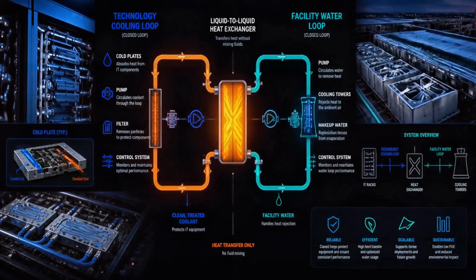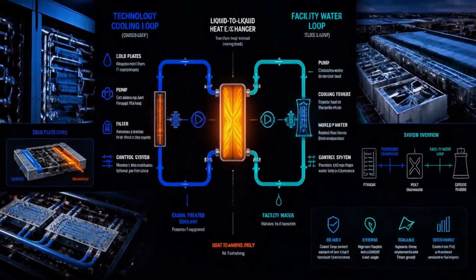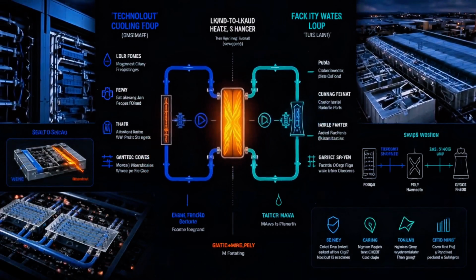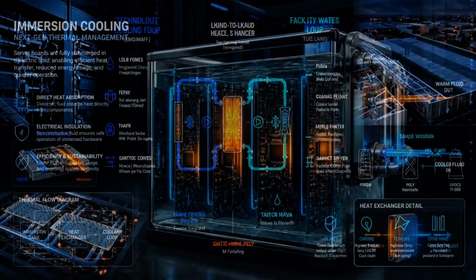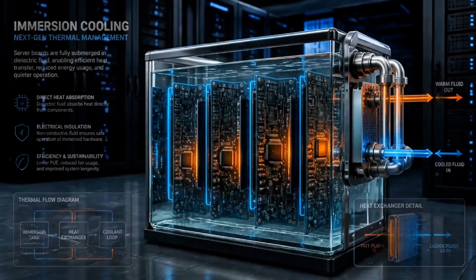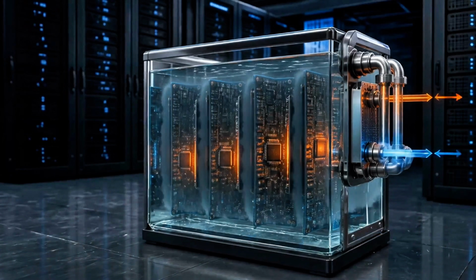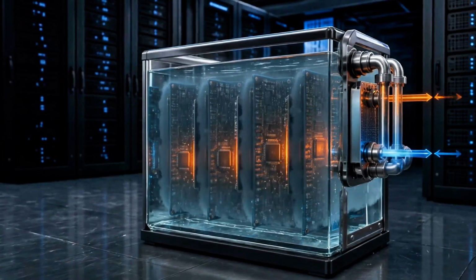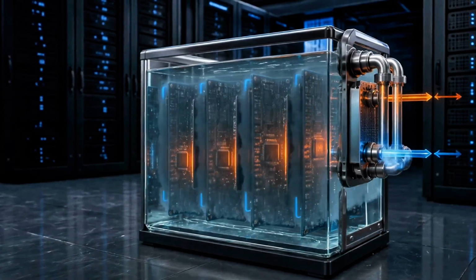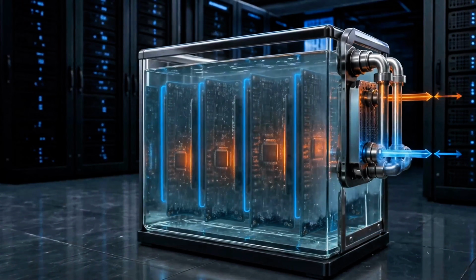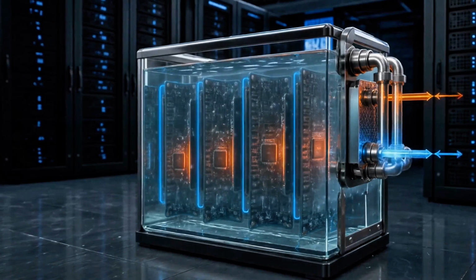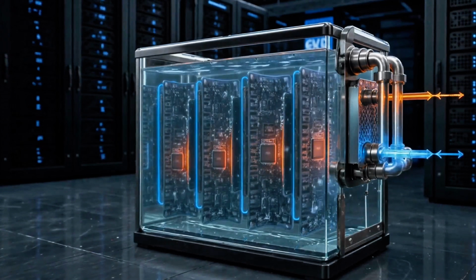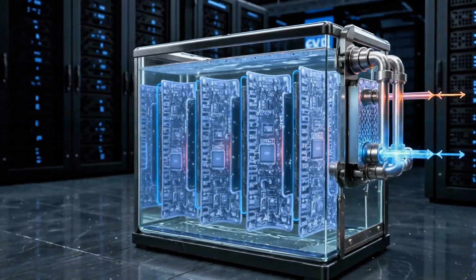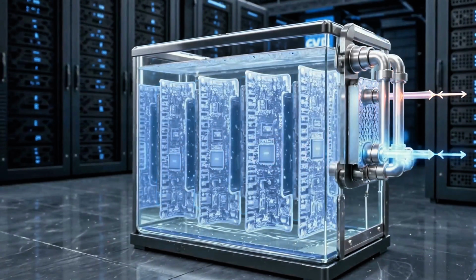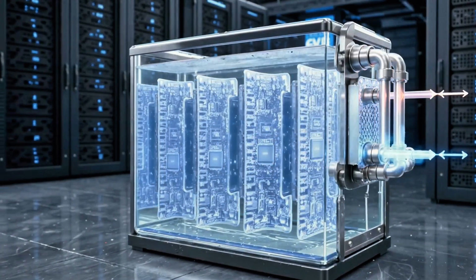The facility loop carries the heat outdoors, where dry coolers, cooling towers, chillers, or other equipment release it into the environment. Another approach is immersion cooling. Specialized computer hardware is placed inside a non-conductive dielectric fluid. The fluid touches the hot components directly and carries heat to a heat exchanger. It can remove large amounts of heat, although installation and maintenance require a different server design.